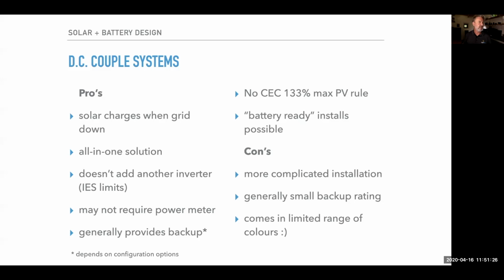So, DC coupled. Glad I got onto that before we finished. DC coupled systems historically were the only way of charging a battery. DC coupling used to be extremely simple: effectively connecting a solar panel straight to a battery was the way we used to do DC coupling. But these days we use charge controllers, because if you directly connect a solar panel to a battery, you're going to get very inefficient charging and possibly overcharging of that battery unless you manage it. But it does mean that you've got a dedicated way of charging the battery. You don't need anything else. You don't need the grid. You don't need AC sources to be around. It's just going to charge. The sun shines and you charge the battery.